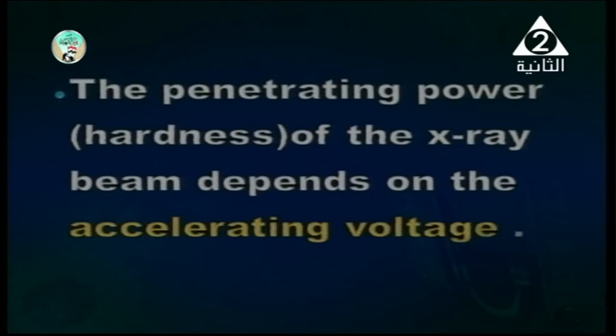The penetrating power, the hardness of the X-rays, depends on the accelerating voltage.